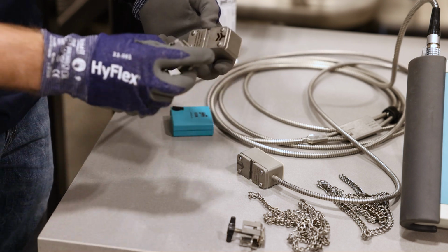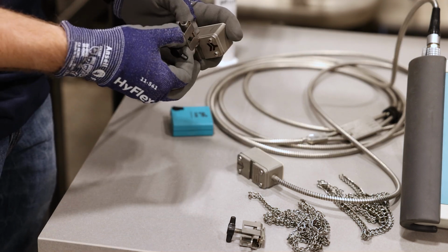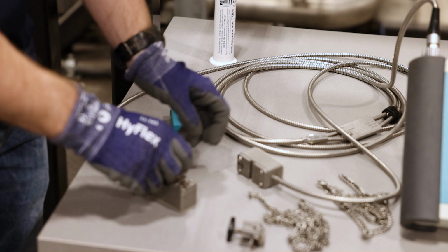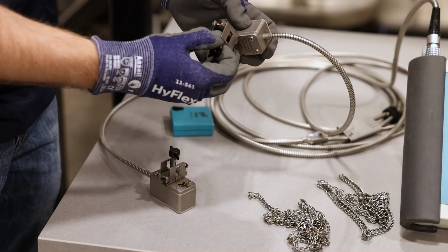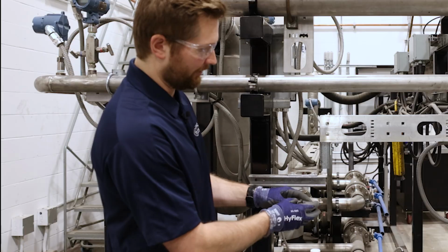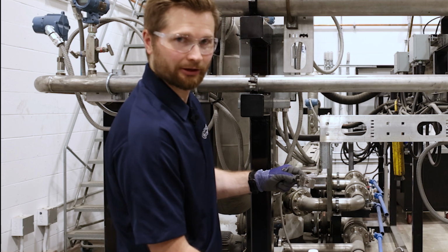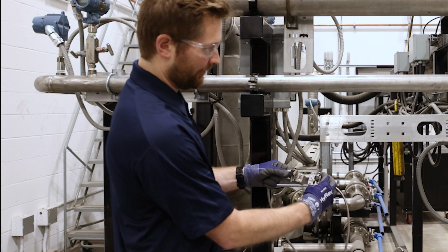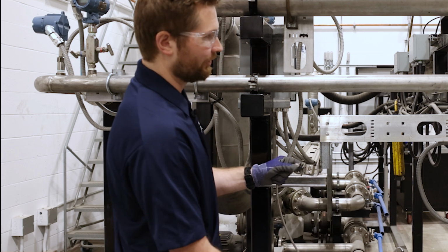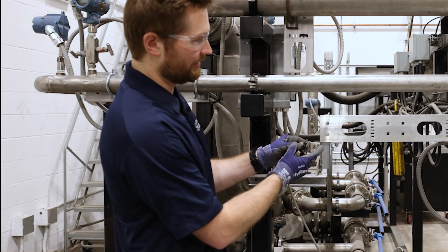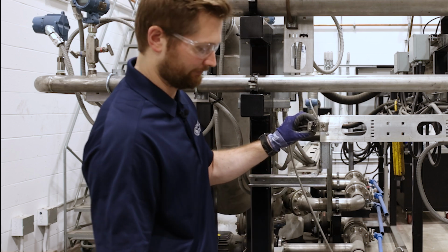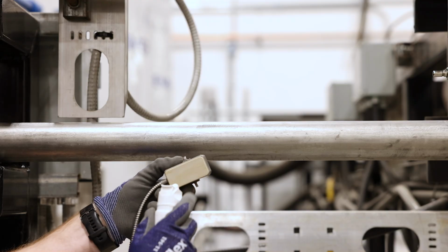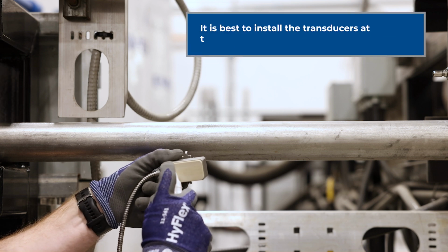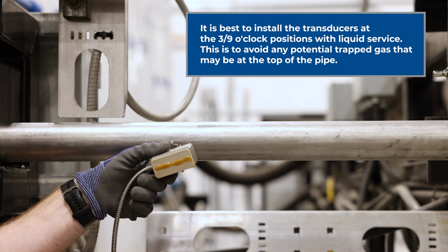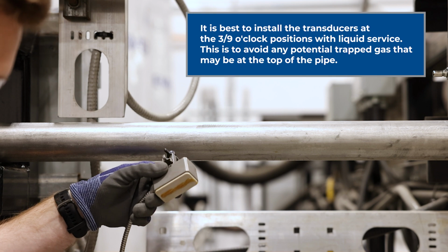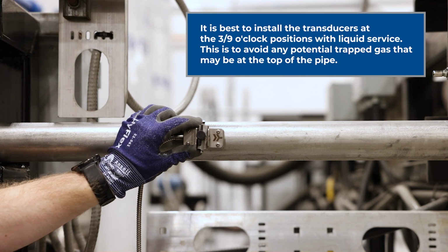We'll install the mounts on the transducers, and these just slide in. The transducers have a directional arrow on them to go with the flow. Since our flow is blowing this way, we need to install the tail of the transducer here. We'll now put some acoustic gel on the bottom of the transducers and put them onto the pipe.